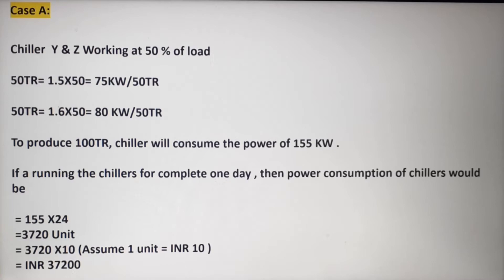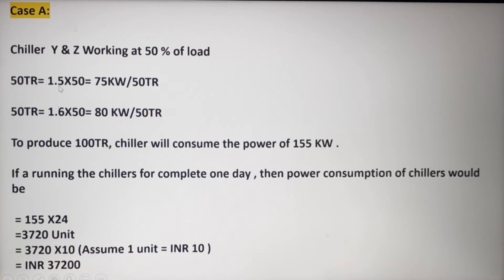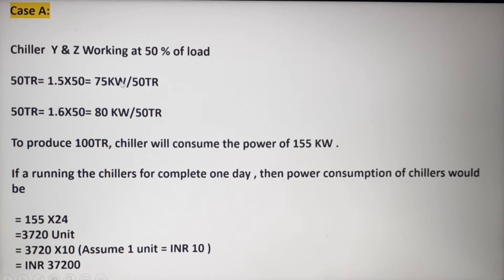In Case A, chillers Y and Z are each running at 50% load. Since each chiller's rated capacity is 100 TR, each one is handling 50 TR. Chiller Y consumes 1.5 kW per TR, so 1.5 × 50 = 75 kW to produce 50 TR of cooling. Chiller Z consumes 1.6 kW per TR, so 1.6 × 50 = 80 kW to produce 50 TR of cooling.